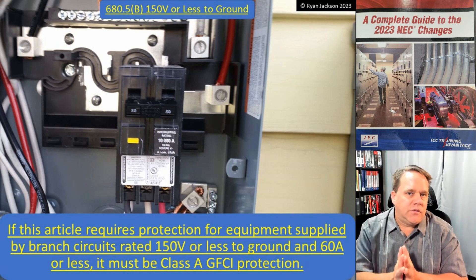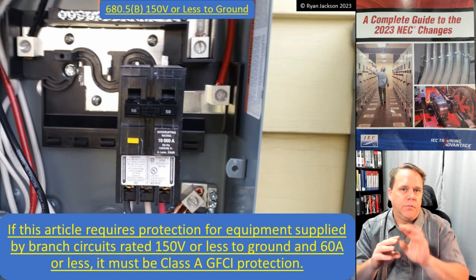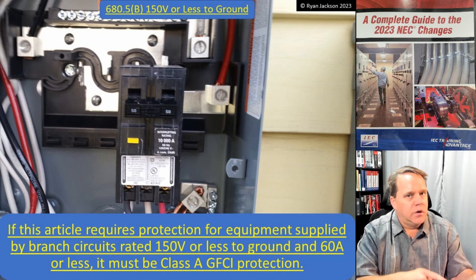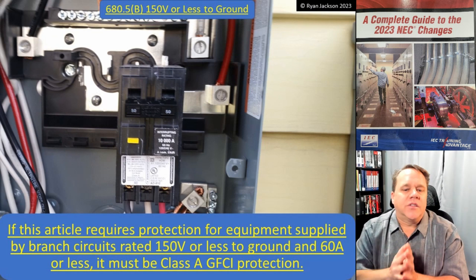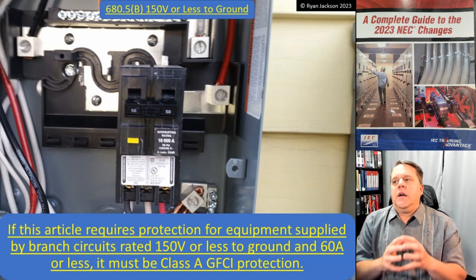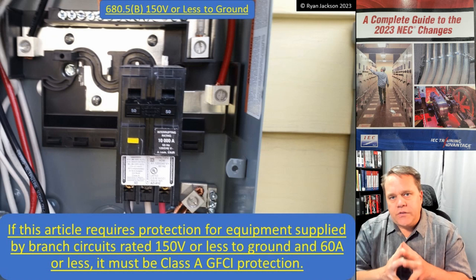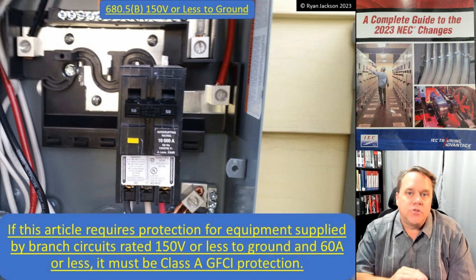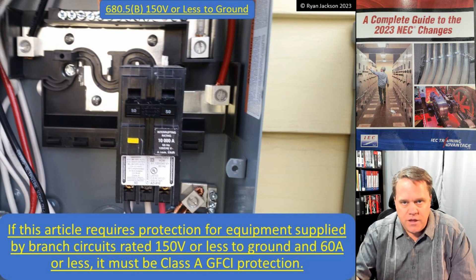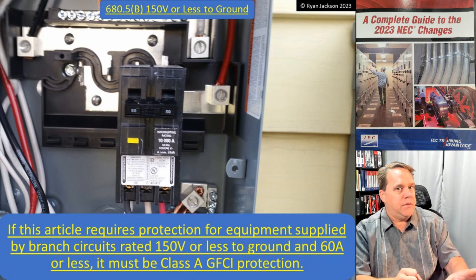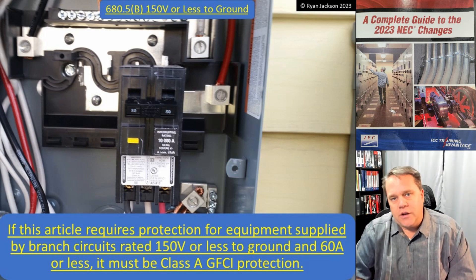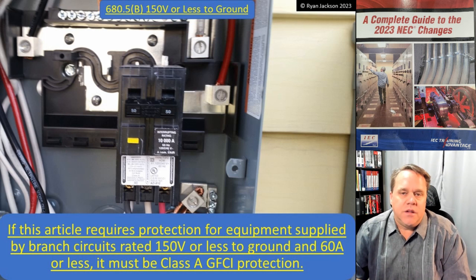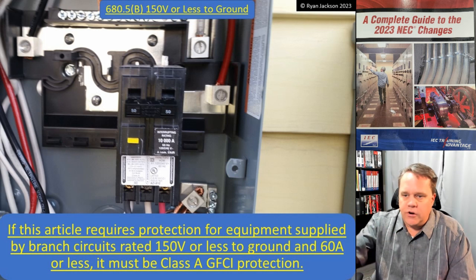A Class A GFCI opens when the difference in current between all the circuit conductors is between four and six milliamps — does not open if it's less than four, must open if it's greater than six. There was a Class B GFCI device all the way back in 1968; they haven't been manufactured in over 50 years. So forget Class B — you're not going to find one. If you see an actual Class B GFCI, take a picture and email it to me, because I don't know anybody that has seen one in the last 50 years.